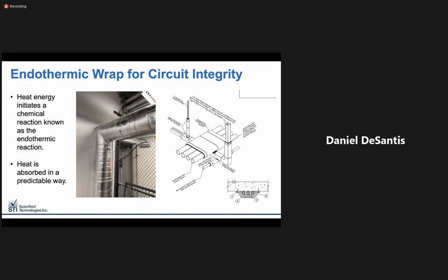Endothermic wrap is applied in layers corresponding to the required fire resistance rating of the protected item. In the image shown here, 4 layers were required to protect this item for 2 hours for a 2-hour fire resistance rating.